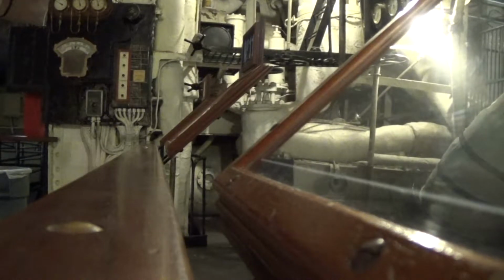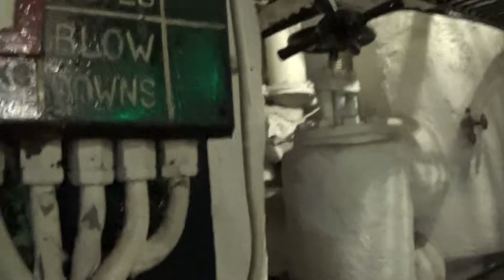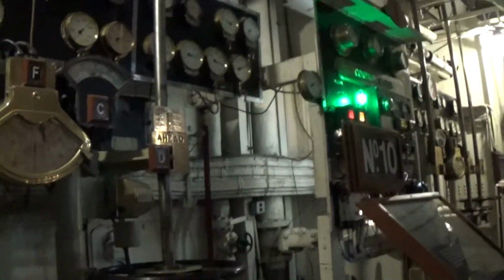Feed water entering the steam drum located on top of the boiler passed to 3 lower water drums which pass through the furnace in pressurized steel tubes, where it was turned into steam by spraying preheated bunker C fuel oil into the furnace, firing it and raising the temperature of the furnace to approximately 3,700 degrees Fahrenheit. At full power, the boilers consume more than 40 tons of fuel oil per hour. In the first stage of steam generation, saturated steam was produced in large vertical tubes and passed to the upper half of the steam water drum. This saturated steam was then passed back into the furnace, where it was superheated in small bore tubes and fed into a superheater header or drum, then passed to the engines at 400 pounds per square inch and 700 degrees Fahrenheit. The hot exhaust gases from the furnace were vented out through stack uptakes or funnels. Numbers 1 and 2 boiler rooms to the forward stack, numbers 3 and 4 boiler rooms to the center stack, and number 5 boiler room to the after stack.